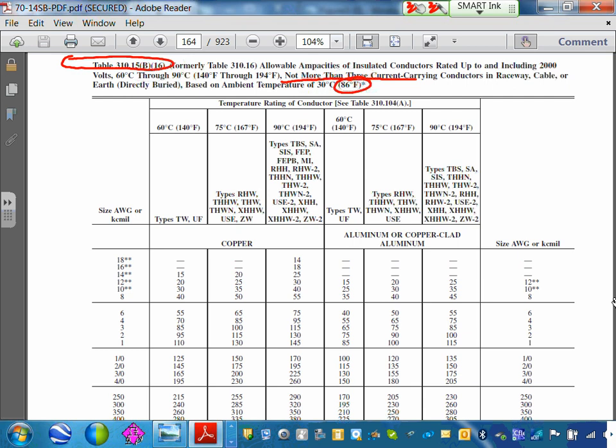Am I making sense? Okay. Now this guy, I want to put them in green. These are the melting temperatures. You're looking at them right in here. This guy and up to this guy, Fahrenheit or Celsius. What are they? These are the temperature ratings of the conductors. They come in 3 categories. I always know them in Celsius: either 60 degree, 75, or 90. You're going to hear these all the time, Celsius, with the Fahrenheit equivalent right next to them. This one you guys are looking at is 90. THHN is considered 90. What does that mean? I can let the THHN reach 90 degrees Celsius or 194 Fahrenheit before the smoke starts coming out.